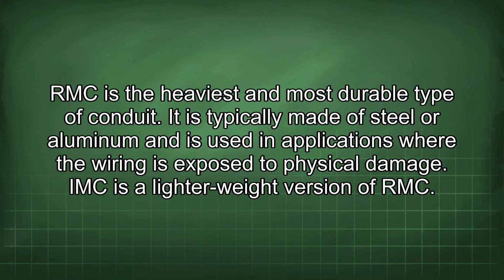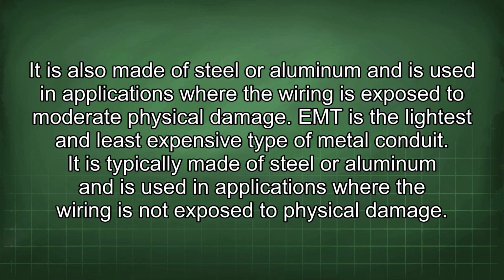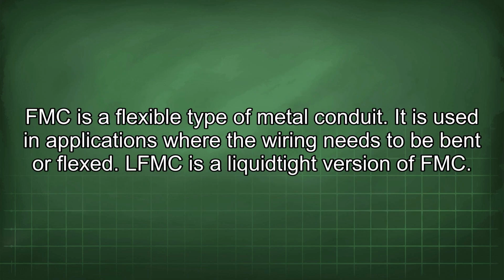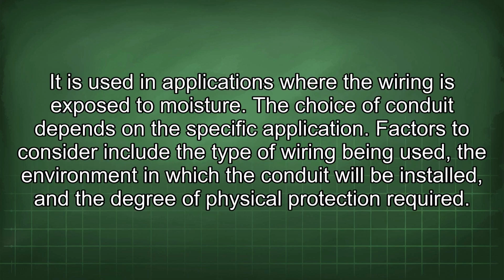exposed to physical damage. IMC is a lighter weight version of RMC. It is also made of steel or aluminum and is used in applications where the wiring is exposed to moderate physical damage. EMT is the lightest and least expensive type of metal conduit. It is typically made of steel or aluminum and is used in applications where the wiring is not exposed to physical damage. FMC is a flexible type of metal conduit. It is used in applications where the wiring needs to be bent or flexed. LFMC is a liquid-tight version of FMC. It is used in applications where the wiring is exposed to moisture.